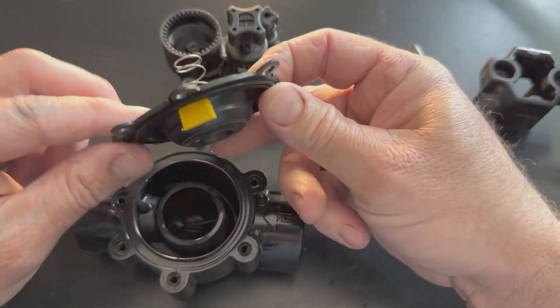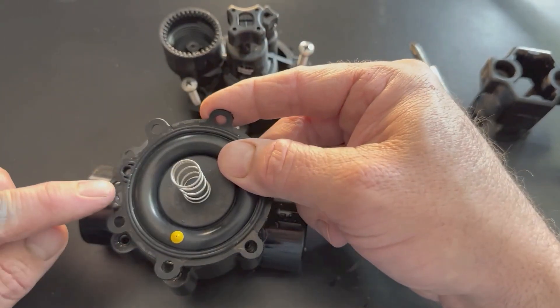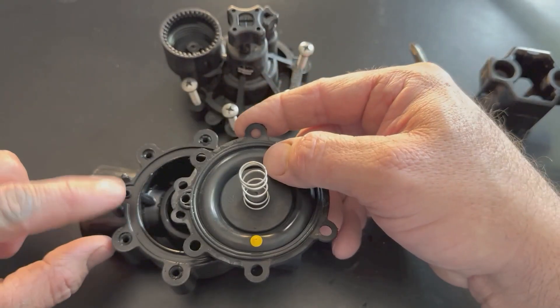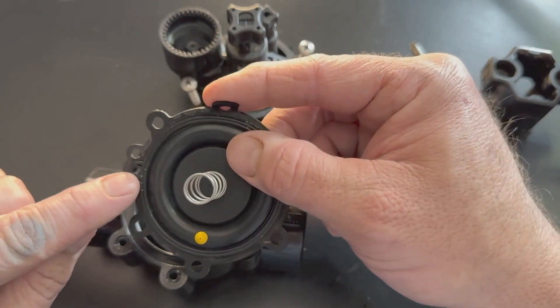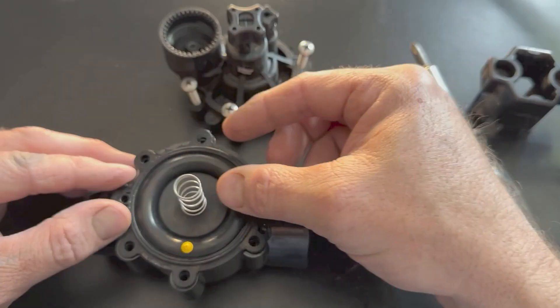This is the diaphragm that you would end up changing if it gets messed up. When you're putting it back on, you've got these two holes that line up with these two little tabs. And you've got to make sure this hole goes right over that because that's where your solenoid goes. That's how it's going to open up.